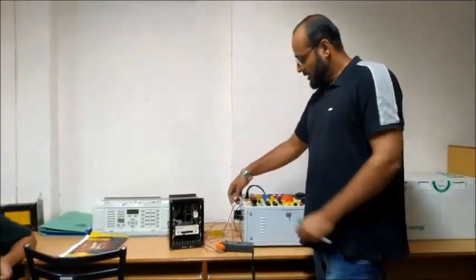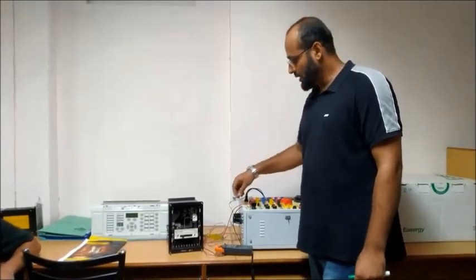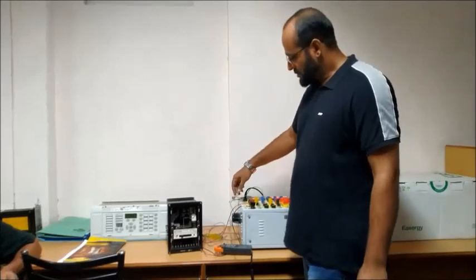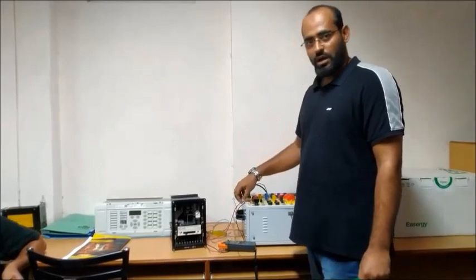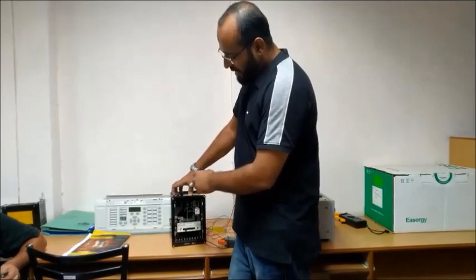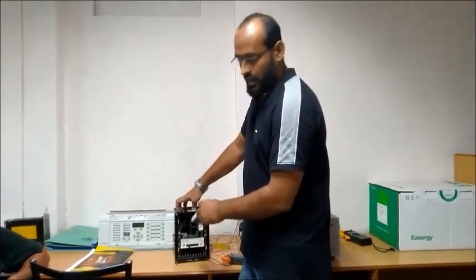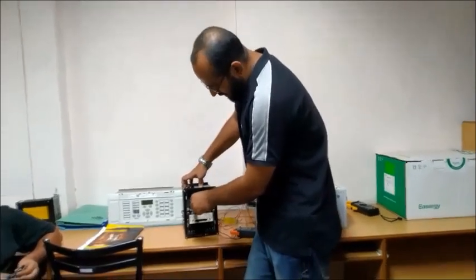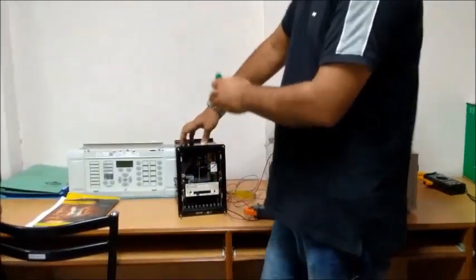When CT, suppose in the field, these two wires are connected with CT secondary and this is connected with our breaker. So when the fault is coming in our field area, the secondary current will come to this relay and when the secondary current is more than our setting value, that time this disk starts rotating and due to rotation this disk will make the contact and trip the breaker.